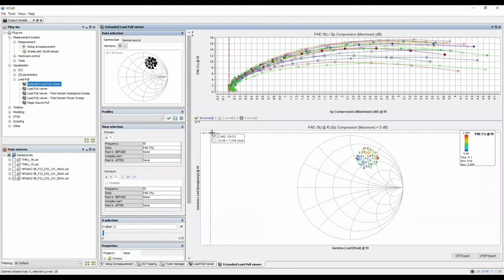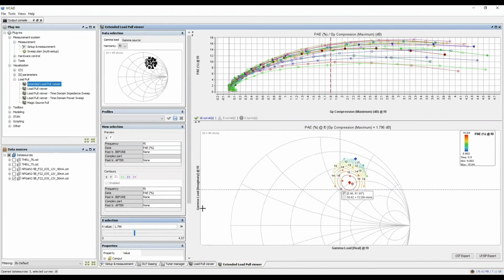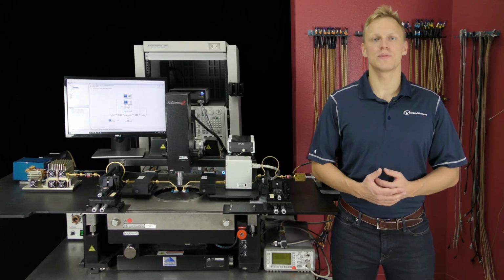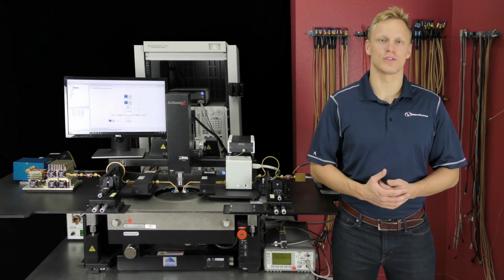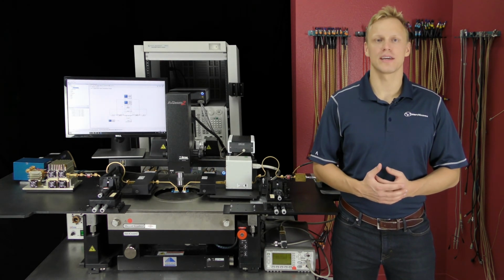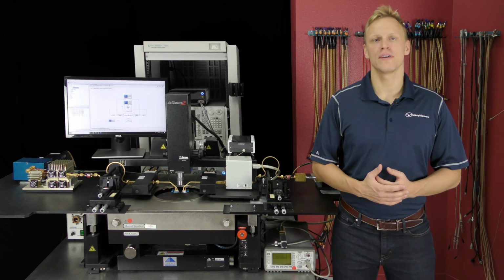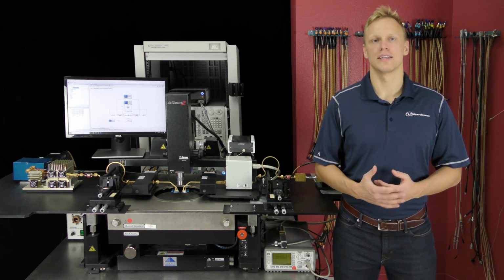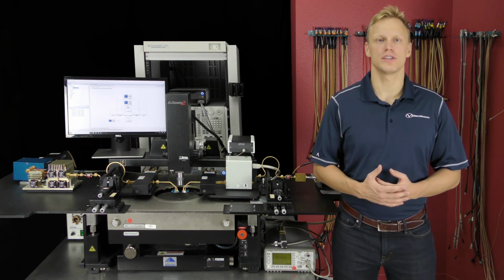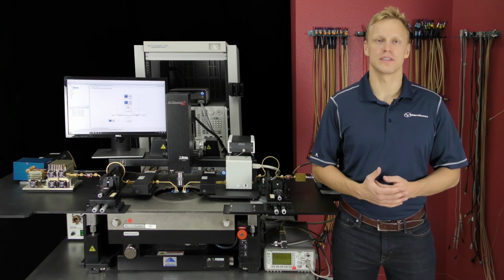After the measurement is finished, we can easily analyze the measurement data using IVCAD's advanced data visualization tools and plot the device parameter contours against the desired gain compression value. In summary, Maury's millimeter wave hybrid active load pull solution enables high-power device characterization between 75 and 110 GHz under linear and non-linear operating conditions as a function of load impedance.